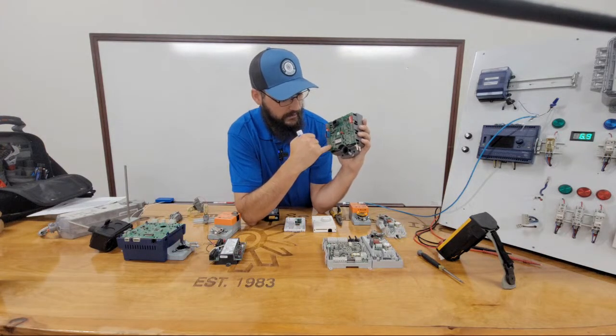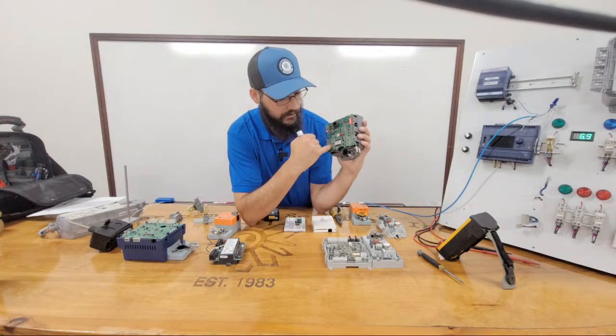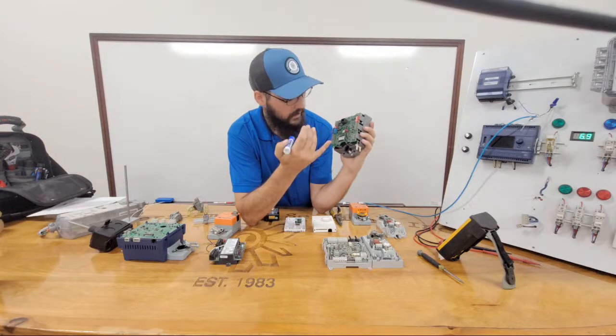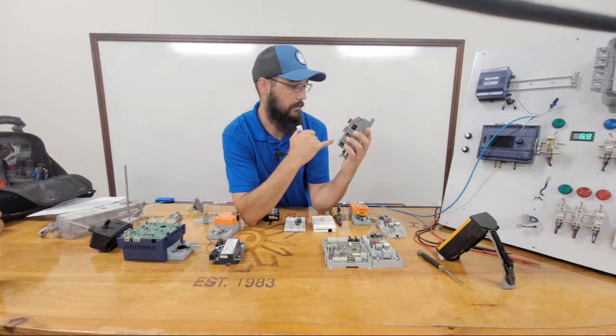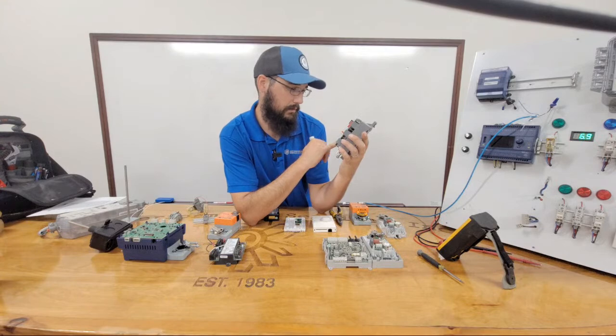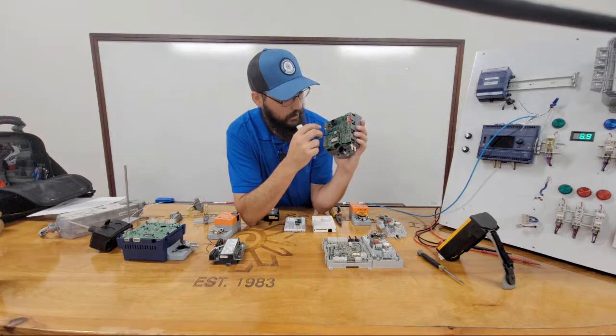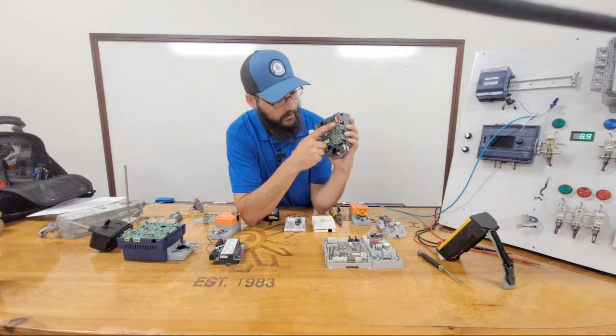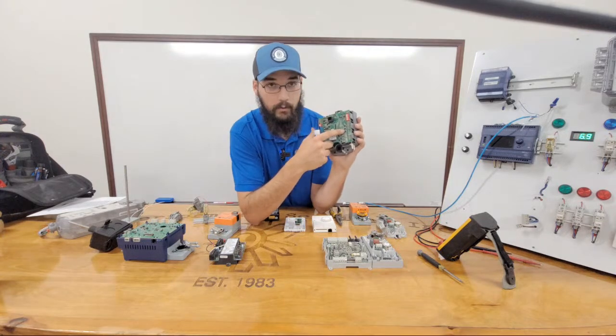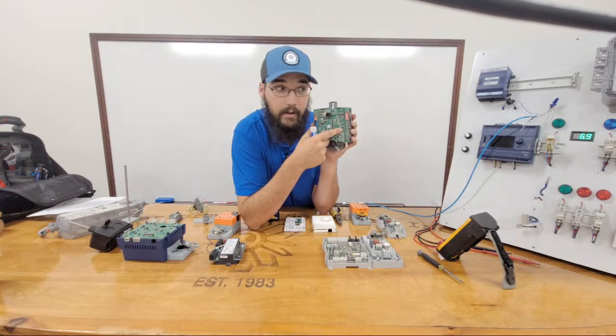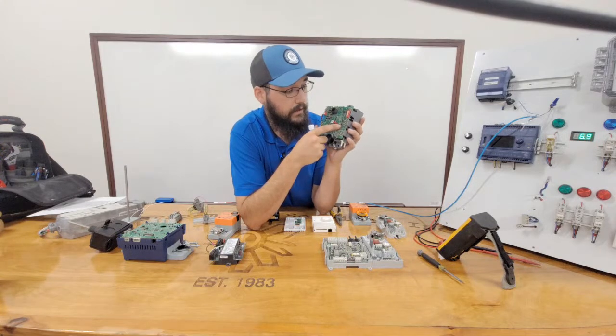I can tell you by looking at the design that this particular side has analog inputs or outputs of some style. These particular ones are probably going to be outputs. Over here, these terminals are going to be binary outputs specifically.